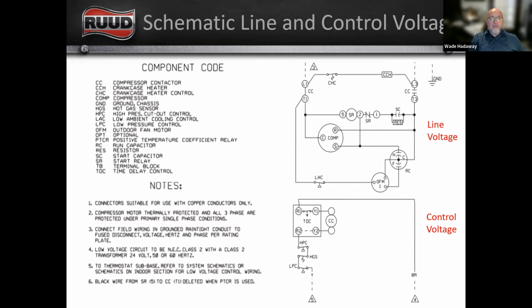So as we back out of our schematic control, not only do we have the line voltage, or the 240 volt side of it, but we also have the control voltage, or the low voltage side. Right? And so we've got our contactor, right? CC is our compressor contactor. But then on the bottom, we've got the contactor connections for our low voltage.